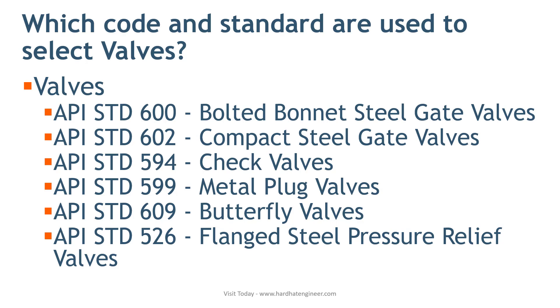API standard 594 covers design, material, face-to-face dimensions, pressure-temperature rating, examination, inspection, and test requirements for check valves with flanged, lug, wafer, and butt welding type ends. API standard 599 covers design for metal plug valves with flanged, threaded, and welding ends in sizes NPS 1 inch through NPS 24 inch. API standard 609 is for butterfly valves with double flange, lug, and wafer type.